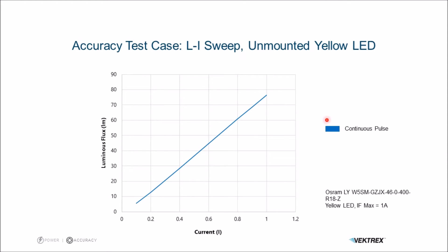It's an LI sweep with a continuous pulse measurement. Here we can see the sweep from low current to high current is pretty linear — this happens to be a yellow LED. We can do the same sweep with single pulse, and we see it's a little bit less linear; it's actually curved down and ends about 25% below the continuous pulse. The same sweep with DC mode is even more pronounced in curvature — in fact, it's 70% down at the final highest current.